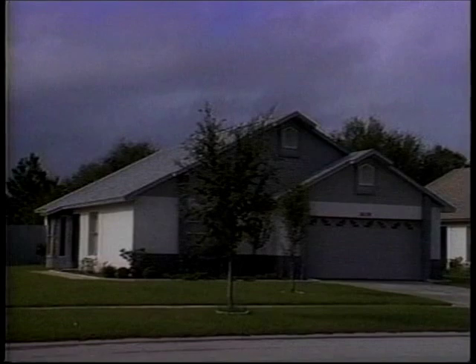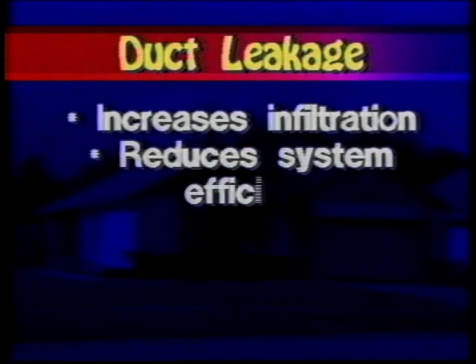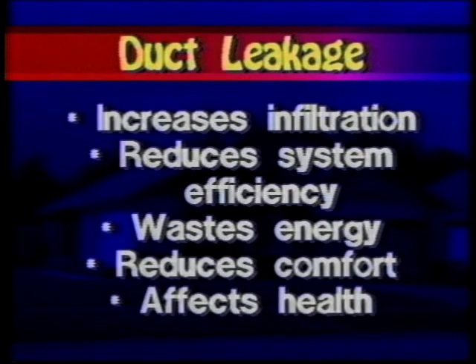Duct leakage affects homes in many ways. Most obviously, it increases infiltration, which is air leaking into or out of the house. And because of increased infiltration, duct leakage reduces the efficiency of heating and cooling systems, wastes energy, and may reduce household comfort. Duct leakage also affects health and safety. Air pollutants may be drawn into the house from the garage, attic, soil, or combustion equipment by duct leaks.